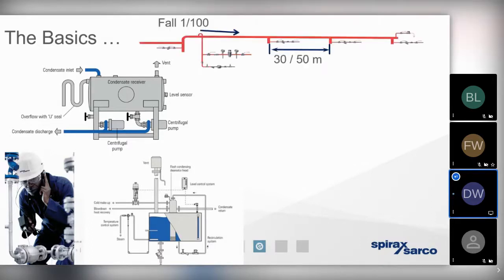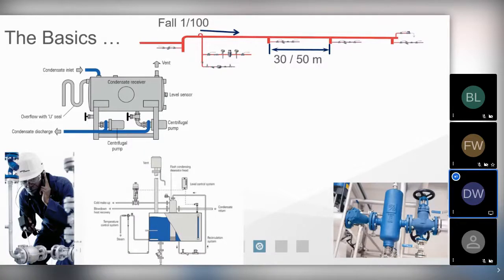We also know that we need to engineer the steam distribution network to remove and recover that liquid condensate. Two benefits there: it keeps the steam as dry as we possibly can, meaning there's more energy contained within the steam, so the process is going to take place more efficiently. But by recovering that liquid condensate, which doesn't have any valuable energy to be used by the process, we can get it back to the boiler house to elevate the temperature of the hot well. We want to dry the steam in the boiler house and ahead of the process. Again, the drier the steam, the more energy there is contained within the steam.